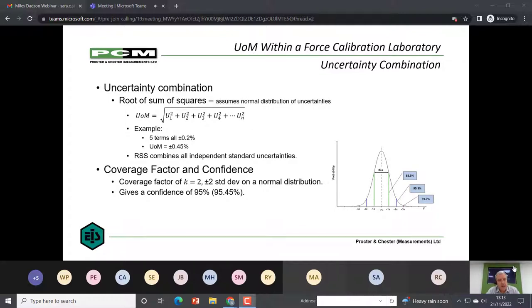So here I've got a formula that shows uncertainty as the root sum of the squares up to the nth uncertainty. As an example, if you had all five terms at 0.2%, the uncertainty by this method would be 0.45%, not just a straight linear addition of all of them, which would lead to 1%. And as with standard deviations, with a coverage factor of k equals 2, that gives you two standard deviations on a normal distribution, a nominal confidence of 95%.